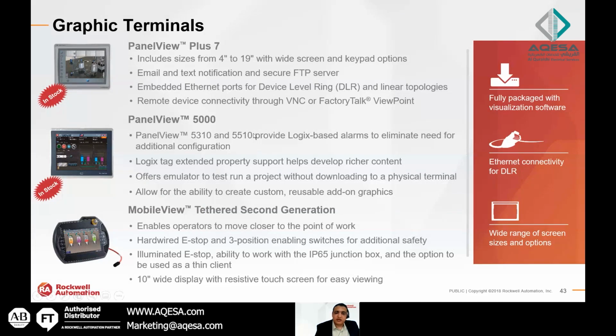PanelView 5000 is programmed with Studio 5000 View Designer. It is not based on FactoryTalk View, it is based on Studio 5000. It communicates directly on the backplane with the CPU, using Logix tag extended properties. You can emulate and test on your computer, and it allows you to create custom, reusable add-on graphics, similar to add-on instructions for the logic CPU, but as add-on graphics for the PanelView 5000 HMI.